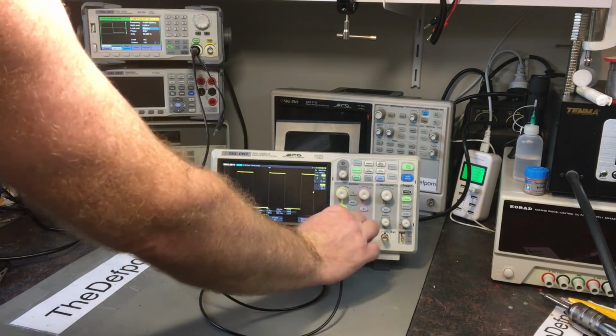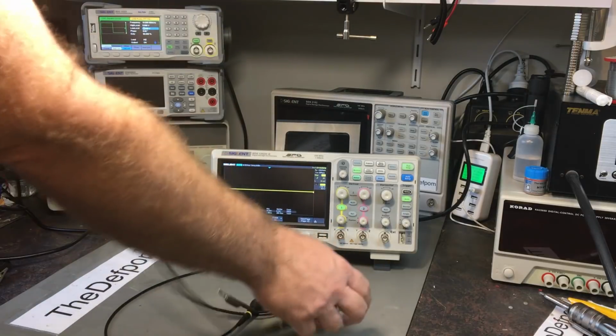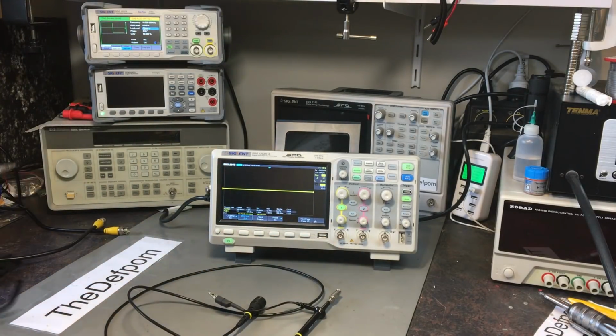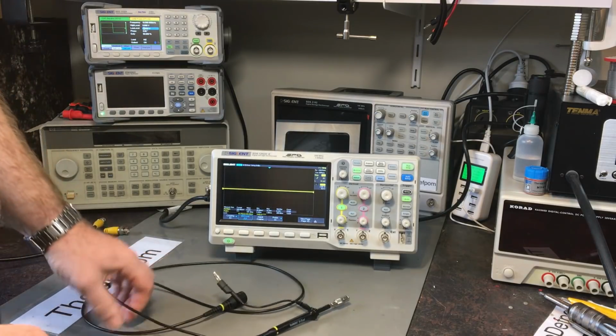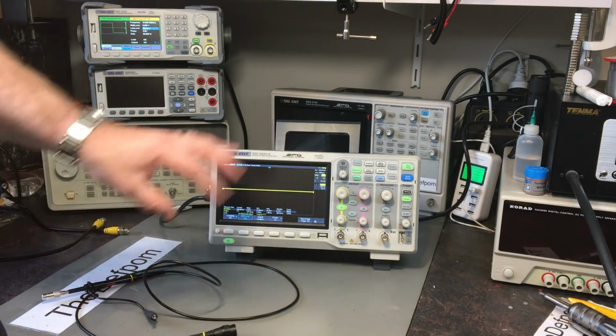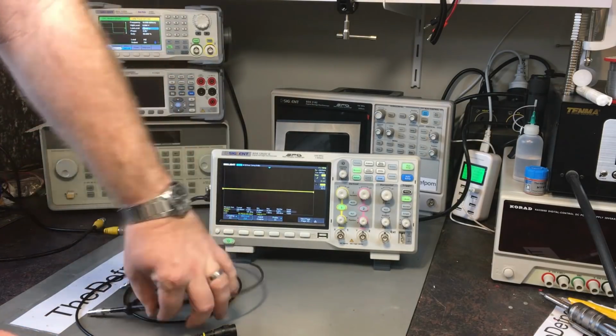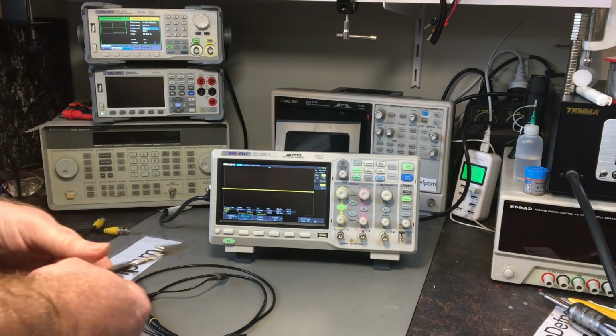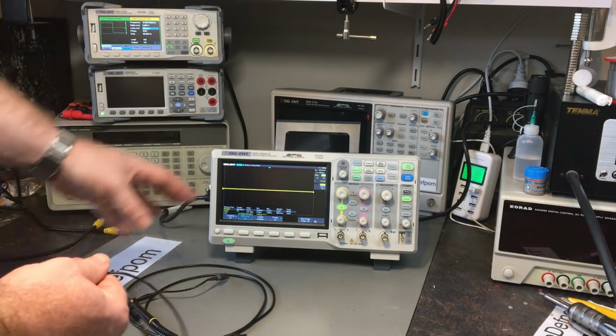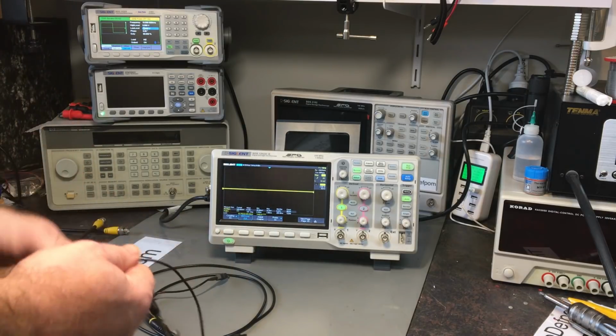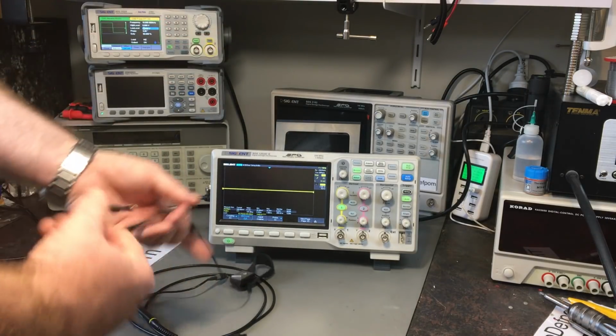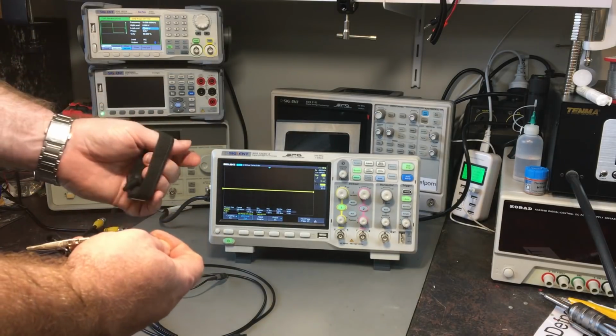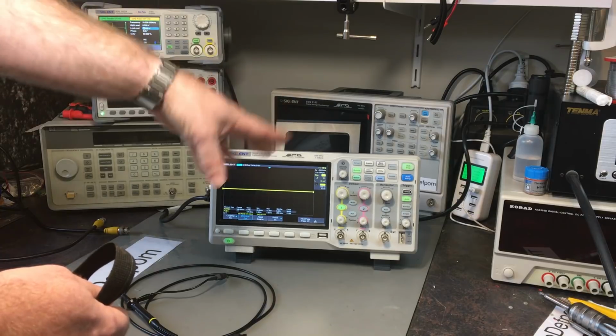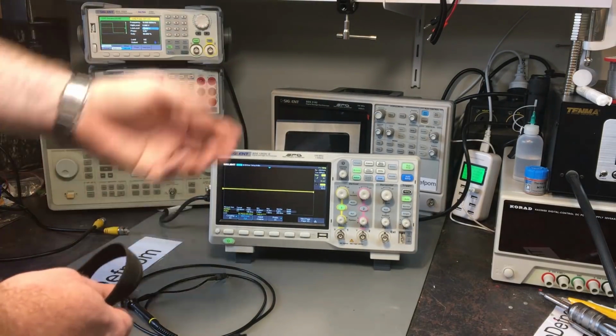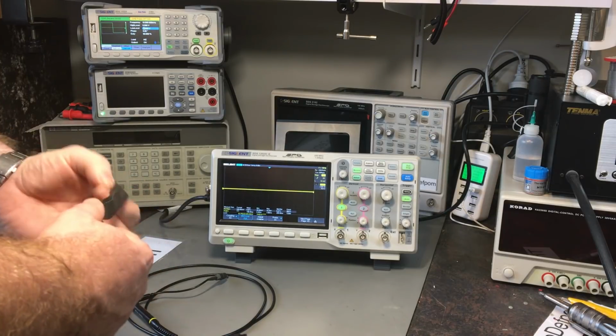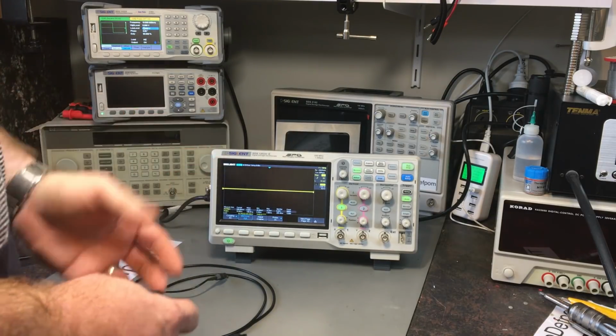Now, there are cautions regarding doing the modification to this unit, and that is that there's high voltage inside it, so you have to be careful of that, and you have to take precautions about what you're doing inside the unit when you pull it apart. Being careful what you touch and making sure you don't expose yourself to anything dangerous. Another thing is ESD protection. So I've got an ESD mat here, so that's okay, it's already grounded. And you also need to make sure you use an earth strap for your wrist, right? So you don't build up any static charge either, because you don't want to accidentally damage the electronics in this thing, because that'd be bad. The idea of this process is to improve the scope, not destroy it.